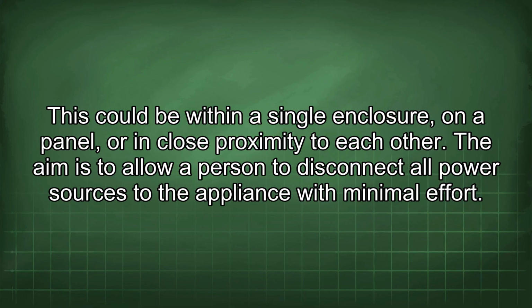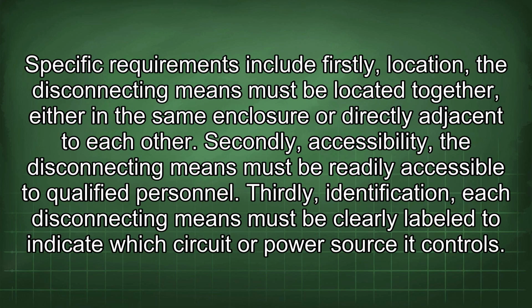The aim is to allow a person to disconnect all power sources to the appliance with minimal effort. Specific requirements include: firstly, location. The disconnecting means must be located together, either in the same enclosure or directly adjacent to each other. Secondly, accessibility. The disconnecting means must be readily accessible to qualified personnel.